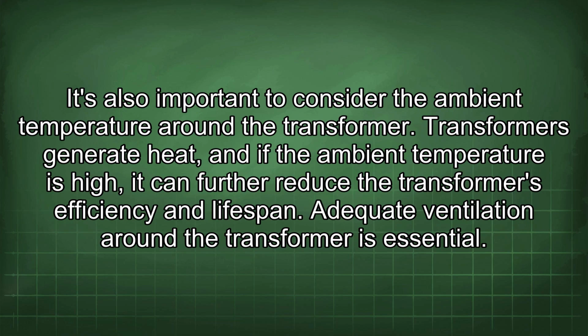It's also important to consider the ambient temperature around the transformer. Transformers generate heat, and if the ambient temperature is high, it can further reduce the transformer's efficiency and lifespan. Adequate ventilation around the transformer is essential.